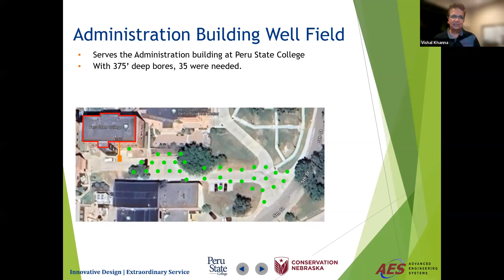To the right side you see the green dots. There's no nice square arrangement — they were just wherever we could put them. They're 20 feet apart, 375 feet deep, and 35 boreholes were needed. It turned out to be a very successful project, just getting rid of a cooling tower and boiler and leaving all the systems inside the same. It became a very efficient system in the administration building.